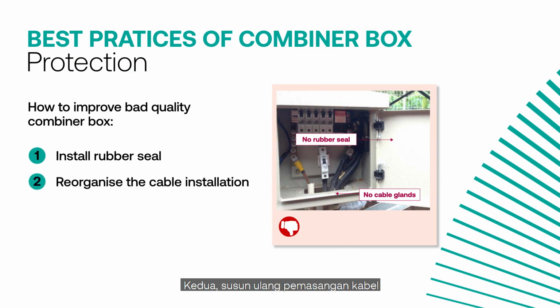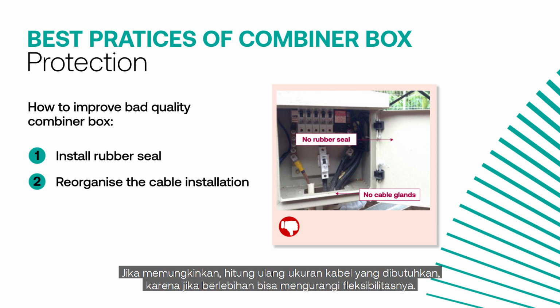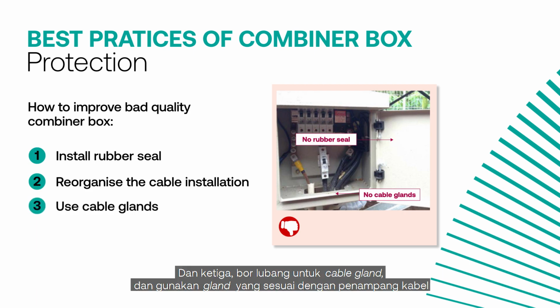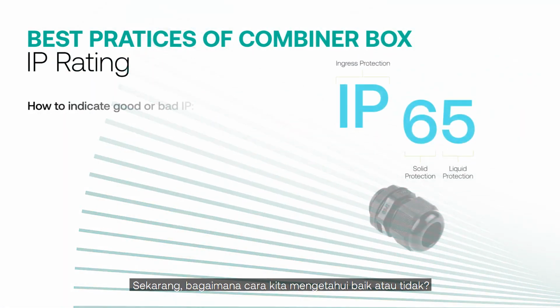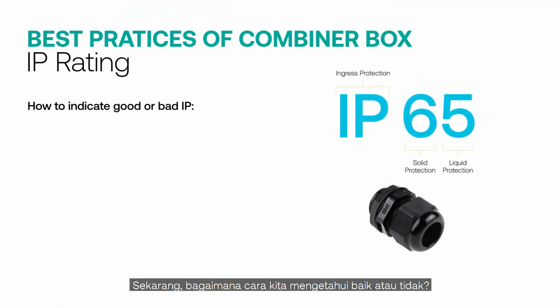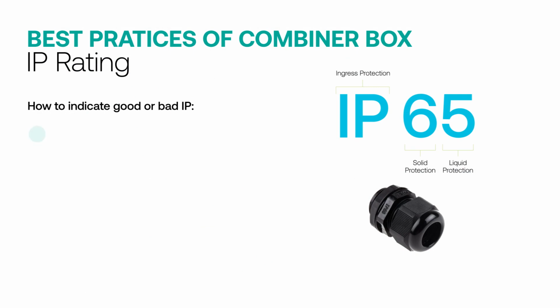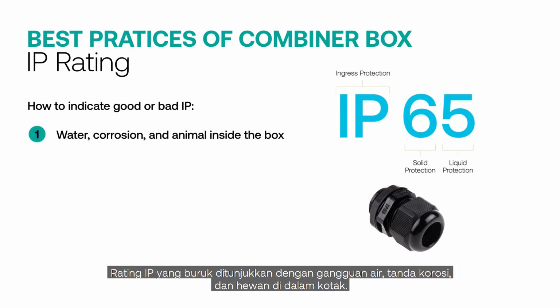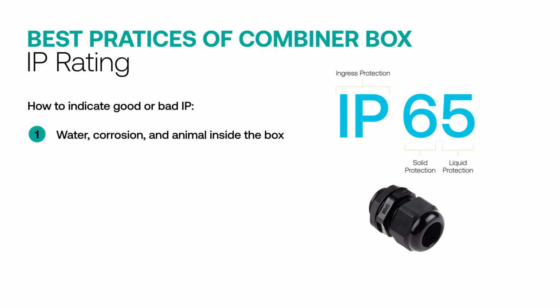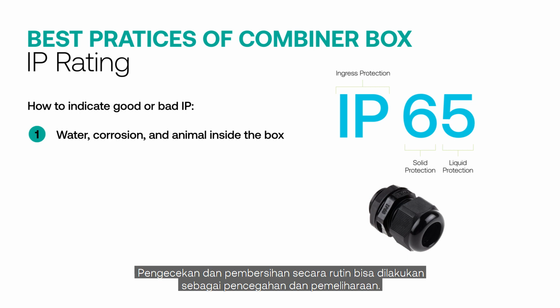Second, reorganize the cable installation. If possible, recalculate the required cable size because overrated cable will reduce its flexibility. And third, drill holes for the cable glands and use glands corresponding to the cross-section of the cable. Now, how can we tell whether the ingress protection of an enclosure is good or bad? Bad IP rating is indicated by water intrusion, signs of corrosion, and animals inside the box. Regular checks and cleaning should be done as preventive maintenance.